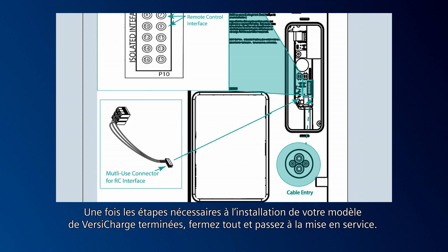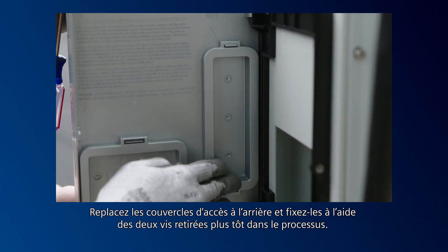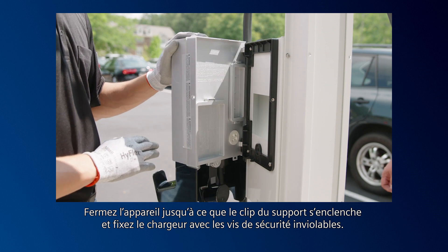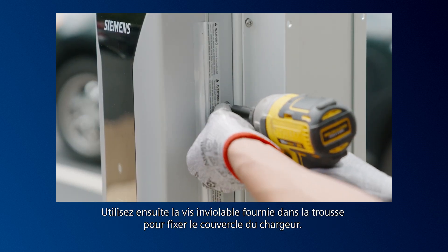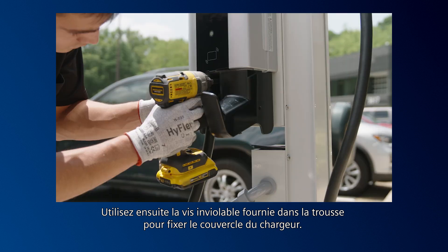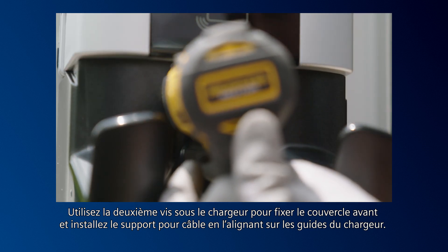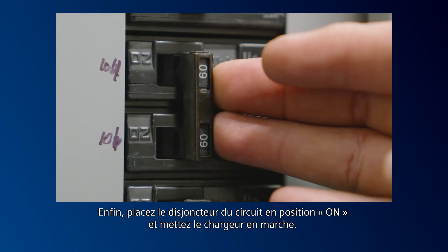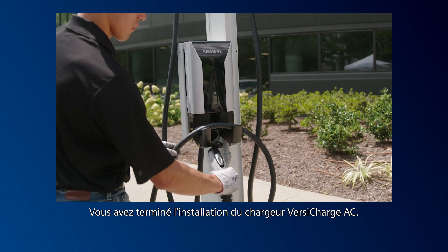Once you have completed the necessary installation steps for your VersiCharge model, close everything up and move on to commissioning. Replace the access covers on the back and secure the barrier with the two screws you removed earlier. Replace the hinged cover and secure it with four Phillips-head screws. Swing the unit closed until the bracket clip engages and secure the charger with the tamper-resistant security screws. Then use the kit-supplied tamper-resistant screw to secure the charger cover and the second screw underneath the charger to secure the front cover. Install the holster by aligning it with the guides in the charger, and with the third kit-supplied tamper-resistant screw, secure the holster to the charger. Finally, turn the circuit breaker for this circuit to the on position and turn on the charger. You have completed the installation of the VersiCharge AC charger.